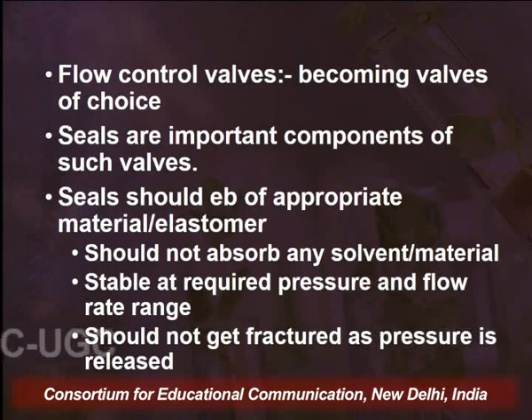and should not get fractured as the pressure is released, because many times in supercritical fluid extraction, once the extract has to enter the separator, the pressure has to be released, or once the extraction is over, pressure has to be released. And it has been observed that certain seals, if they are not properly selected, get fractured whenever the pressure is released to depressurize the system. So such things should not happen with the seals that are used to make control valves.